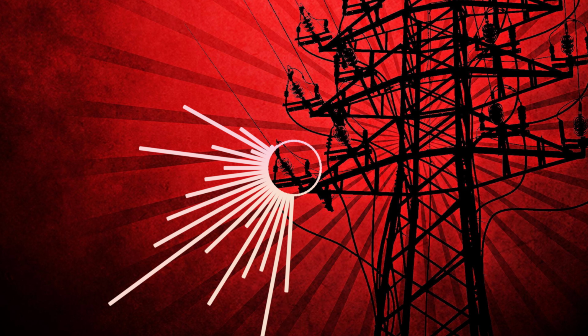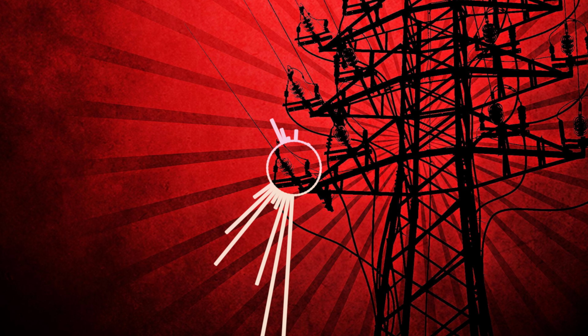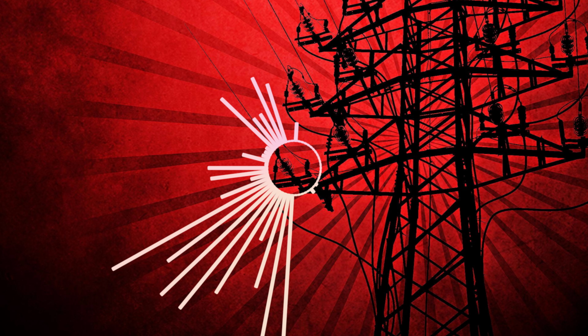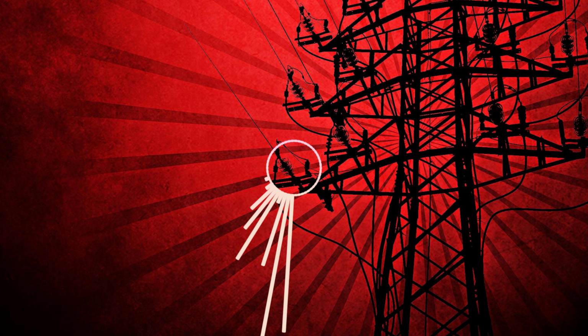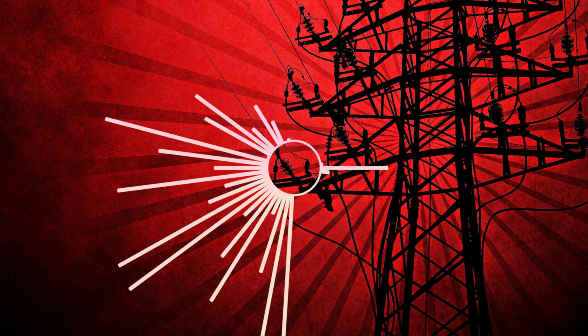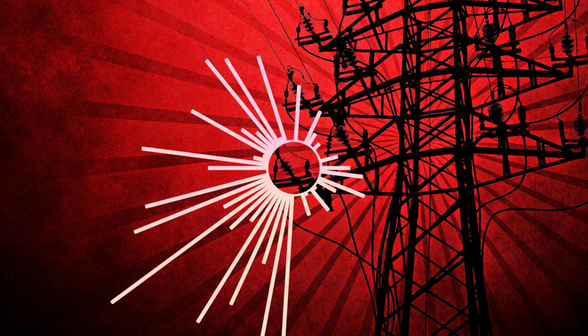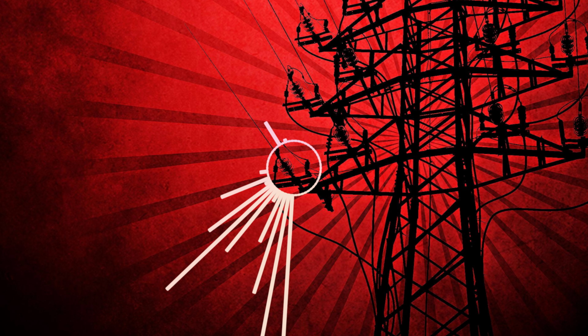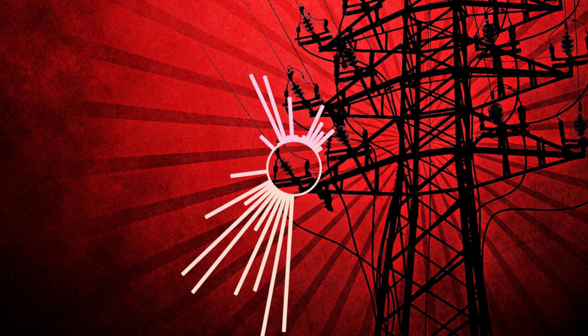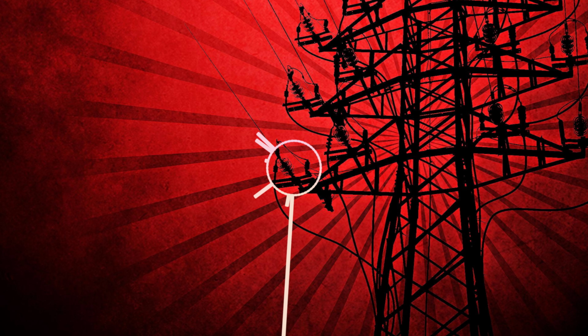The second thing discussed in this rule is marking in larger buildings. In places other than one or two family homes, the disconnecting means must also include information about the circuit source, meaning it should say where the power is coming from. For example, it should indicate if the circuit is being powered from a main electrical panel, a generator, or a different power source.